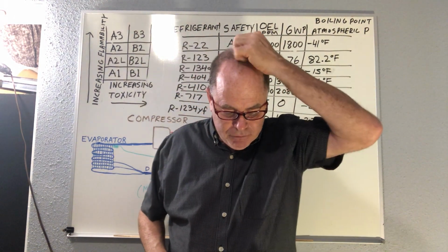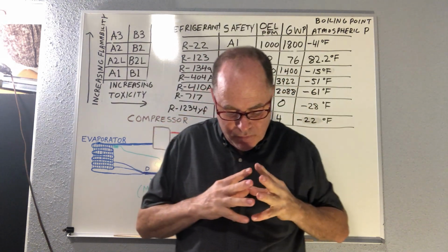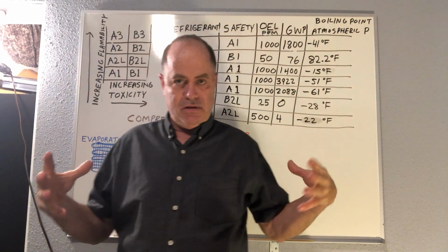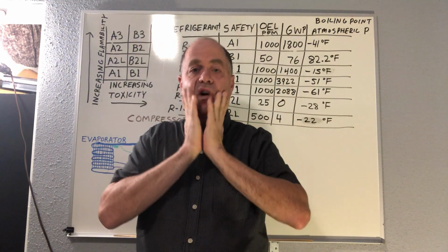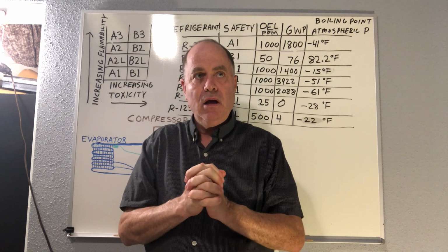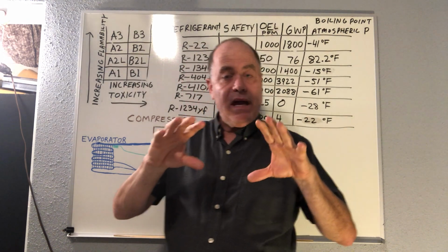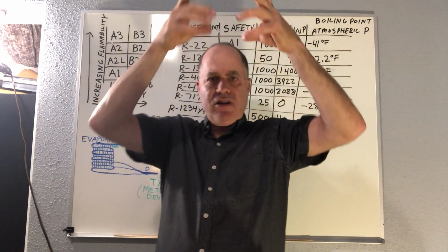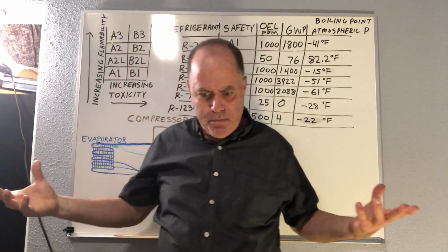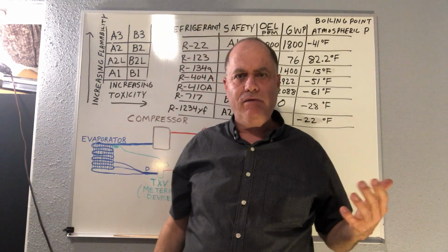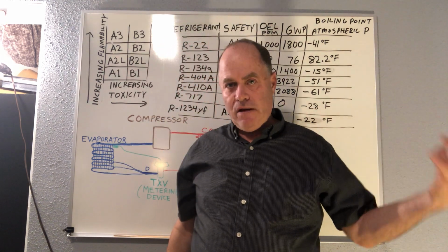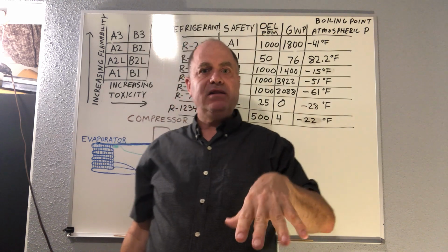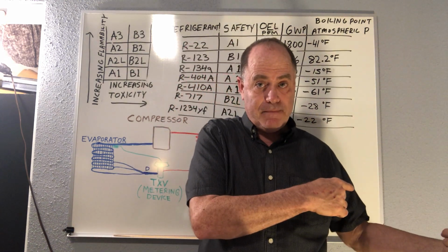And then pressure relief devices are for this reason, that, you know, on these larger systems, like chillers and whatnot that hold tremendous amounts of refrigerant, we have pressure. And the first time I saw this, I'm like, what's this copper pipe? Where does it go? It comes off the top of the condenser. It's going outside. It's open. What is that? Well, that's a pressure relief valve. And I was like, I don't get it. We're not supposed to vent refrigerant, but it's the lesser of two evils. We do vent refrigerant because, like I said, when you burn refrigerant, it becomes toxic.